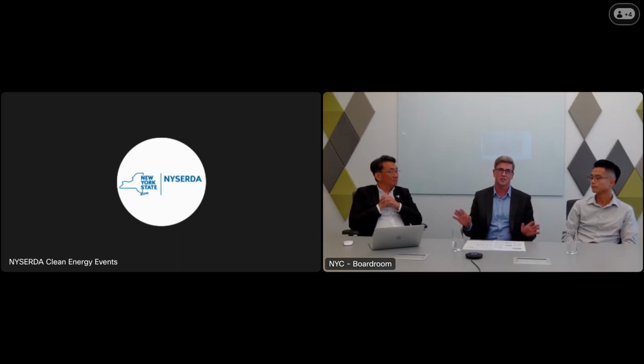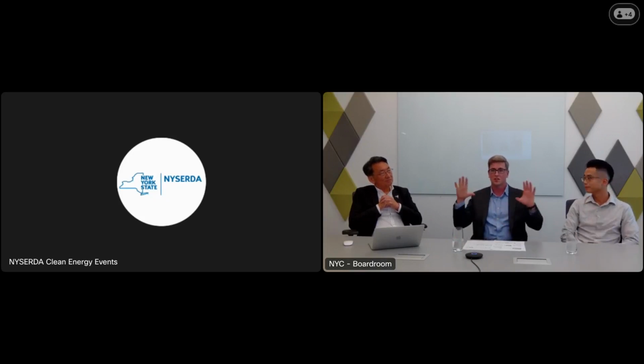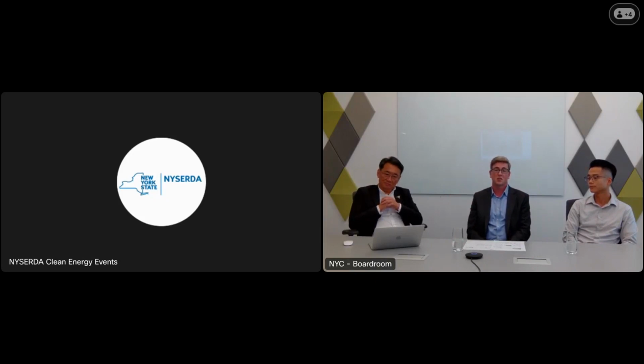So when we took a look at the surge map within the chiller panel itself, we saw all those X's across that pane, it was really pretty full. Normally you would see it not as full as it was at the Josie Robertson Center, but clearing it out, there was no surge condition after it was cleared. The surge count kind of held steady, and it most likely was during the commissioning stages of the construction when they were manipulating the cooling towers. Often, sometimes we see the surge map is actually kind of full.